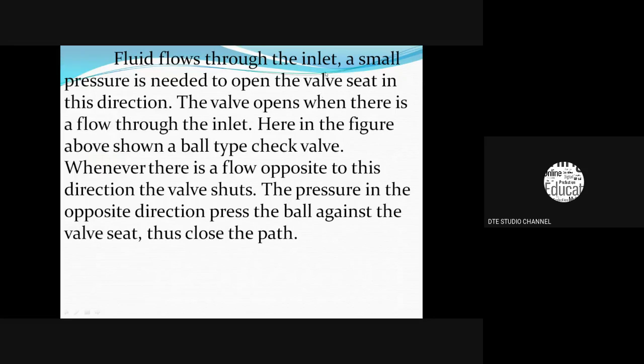Fluid flows through the inlet. A small pressure is needed to open the valve seat in this direction. Whenever the pressure of the fluid is greater than the spring force, then automatically the valve is opened. The valve opens when there is a flow through the inlet. Here in the figure above is shown a ball type check valve. Whenever there is a flow opposite to this direction, the valve shuts. By means of the valve, the inlet port is automatically closed.